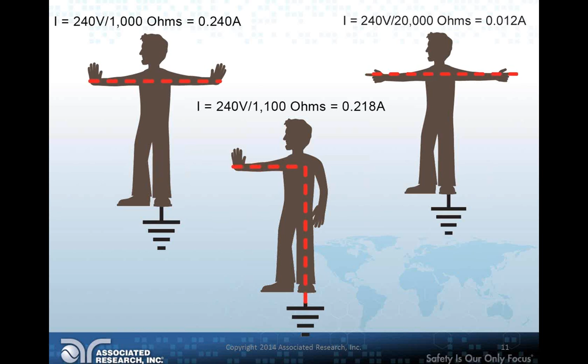That's a lot of current, and you're still in a dangerous zone there. So that gets us into the testing in general. Up to now, we've been talking about human body impedance models, how shocks are going to affect you. Now we really start to want to get into the testing itself, the testing station, but why are we testing in the first place? Why do we run a hipot test or a leakage test or a ground bond test on our products? Well, there's four main reasons.